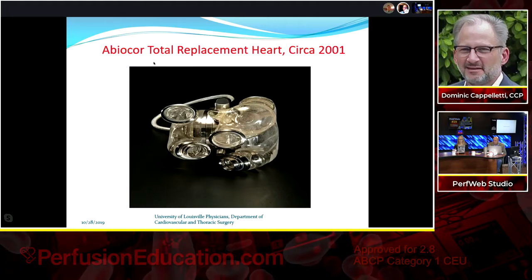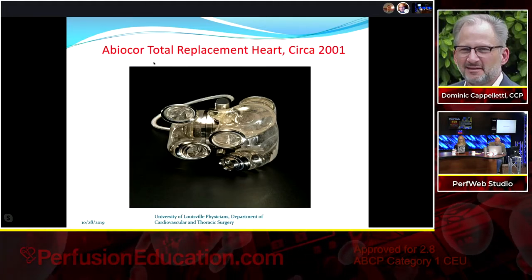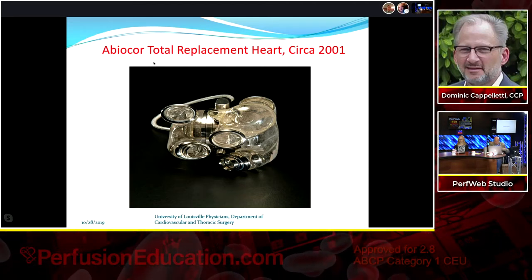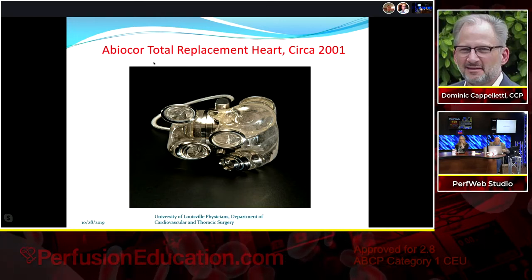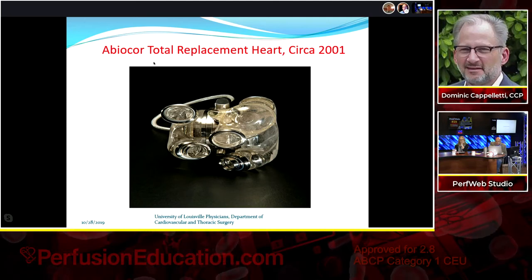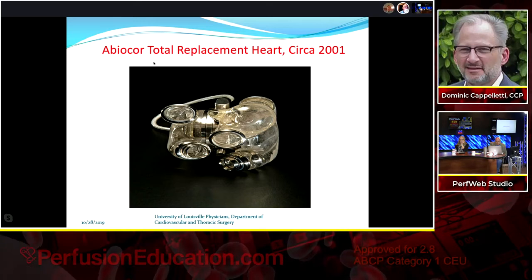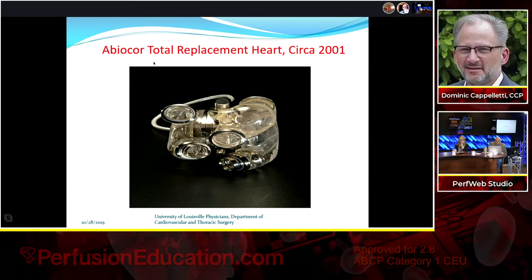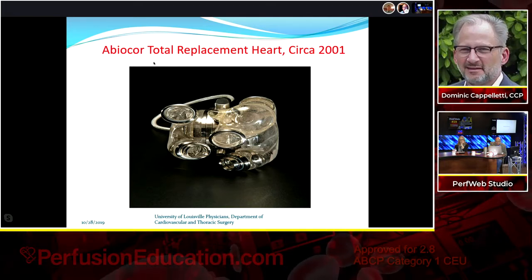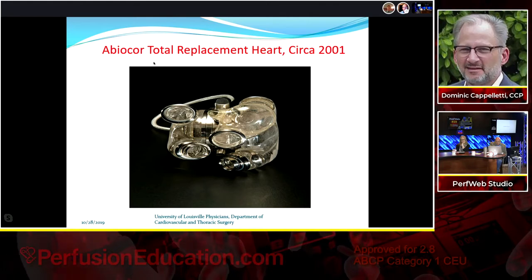The Abiocor is near and dear to my heart — no longer around, but extensively researched in Houston and Louisville. It was a totally implantable total replacement heart with an internal battery and controller. The internal battery lasted 30 minutes to an hour, allowing patients to be completely untethered — swimming, showering, whatever they wanted. It was one of the most complex devices of its time.